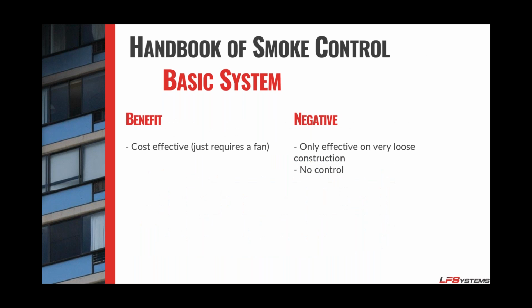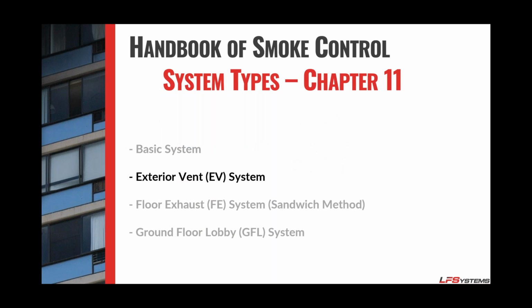So while this is a cost-effective system, it only requires a fan. It's limited to just very loose construction buildings, but again, you have no control over what's happening. So you're really not. So whatever you balance it to during commissioning, that is what you get. So let's look at the second option, the exterior vent system.